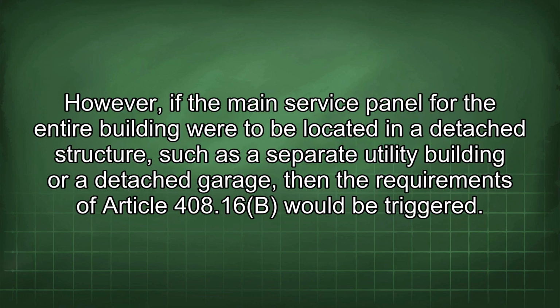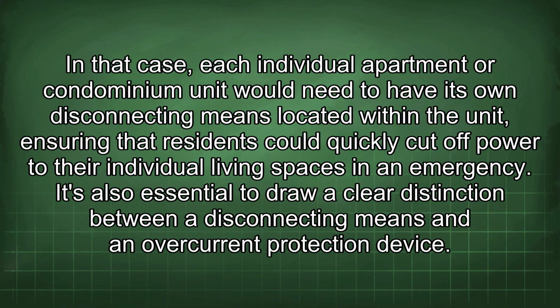However, if the main service panel for the entire building were to be located in a detached structure, such as a separate utility building or a detached garage, then the requirements of Article 408.16b would be triggered. In that case, each individual apartment or condominium unit would need to have its own disconnecting means located within the unit, ensuring that residents could quickly cut off power to their individual living spaces in an emergency.